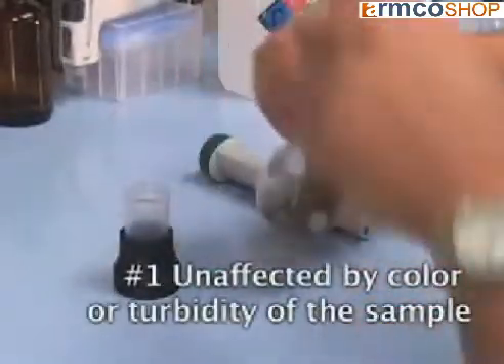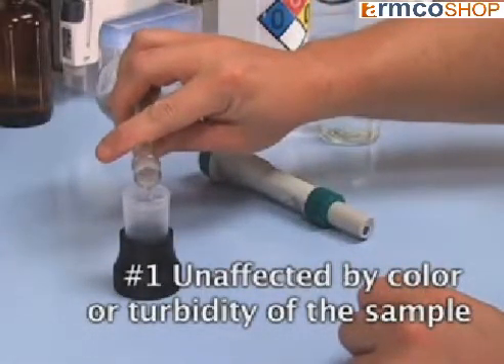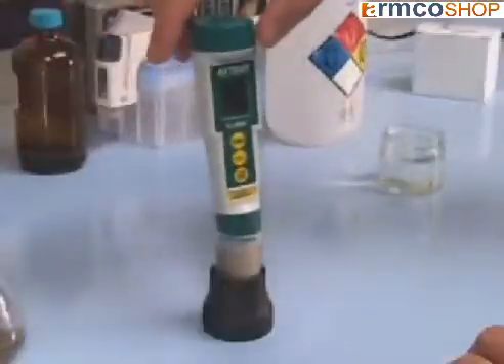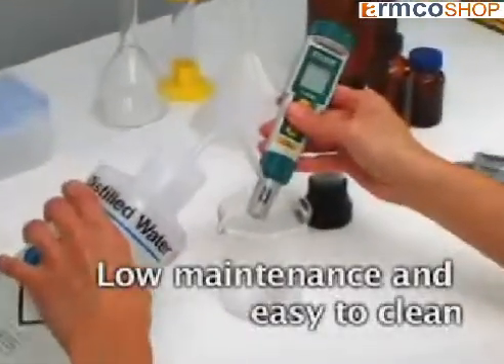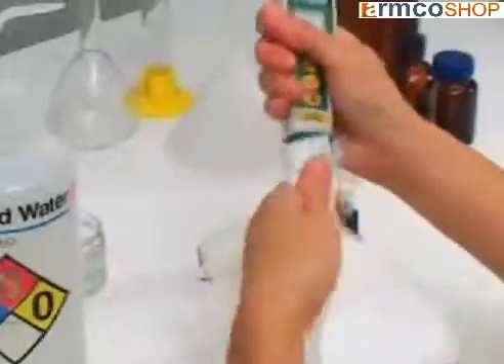Number 1. The technique using a rugged flat surface ISE electrode eliminates error factors that may be caused by light, scratched vials, and color or turbidity of the sample. Its functional design offers low maintenance and is easy to clean — simply rinse the tip with deionized or distilled water and dry off with a dry paper towel.